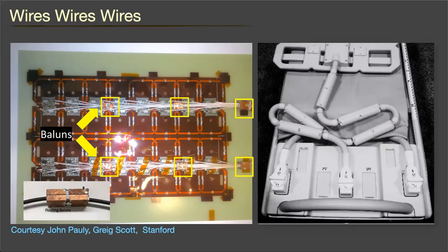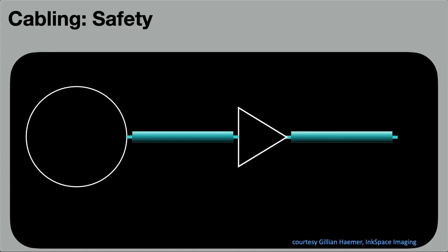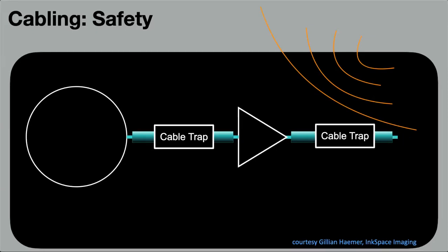So what are these? The coil element is not the only conductor which interacts with the transmit fields. During transmit, very high currents can run on the shield of a coaxial transmission line, endangering the patients. To reduce these currents, cable traps are placed along the conductor within the bore to block unwanted currents, and that reduces them.